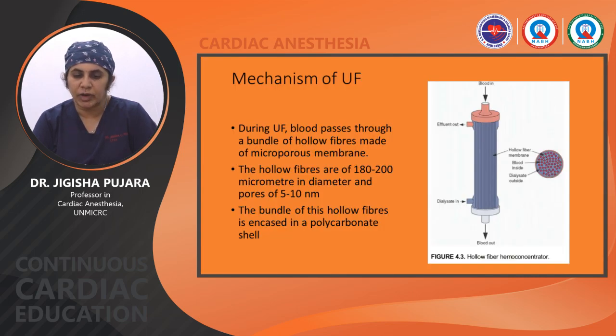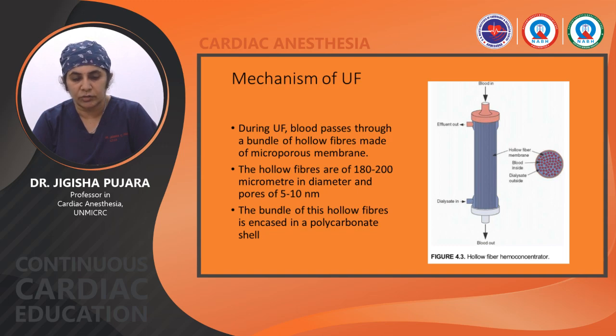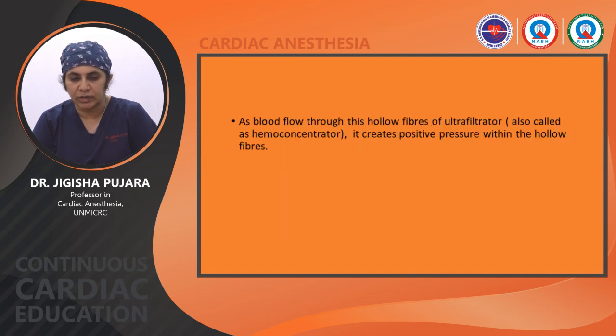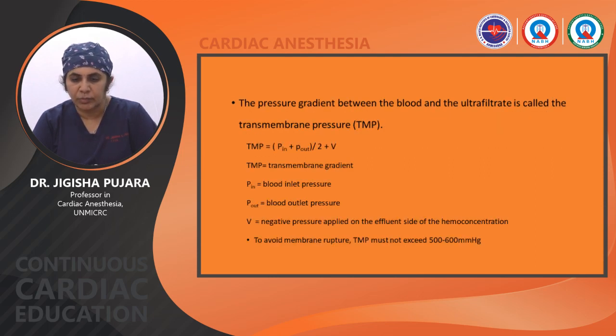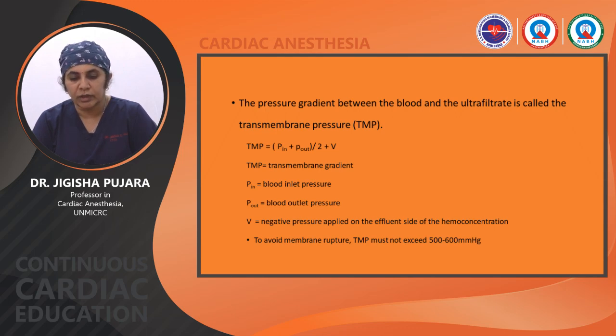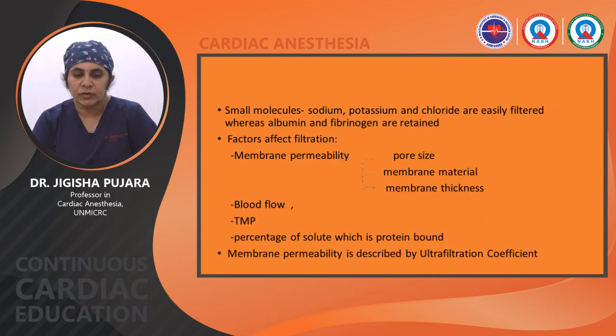Mechanism of ultrafiltration: blood passes through a bundle of hollow fibers made of microporous membrane, 180 to 200 micrometers in diameter with pore size of 5 to 10 nanometers. The bundle is encased in a polycarbonate shell. Blood flow through the hollow fibers of the ultrafiltrator — also called the hemoconcentrator — creates a positive pressure within the fibers. The transmembrane pressure (TMP) equals blood inlet pressure plus blood outlet pressure divided by 2, plus the negative pressure on the effluent side. To avoid membrane rupture, TMP must not exceed 500 to 600 mmHg. Small molecules like sodium, potassium and chloride are easily filtered, whereas albumin and fibrinogen are retained.